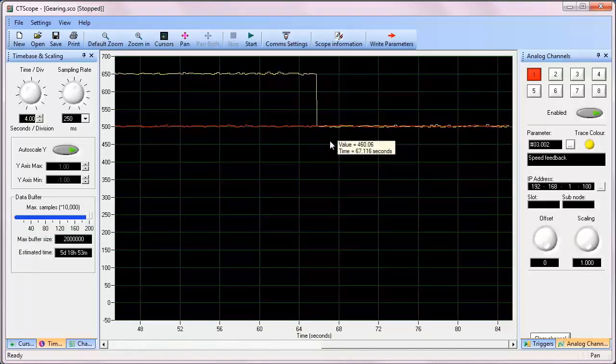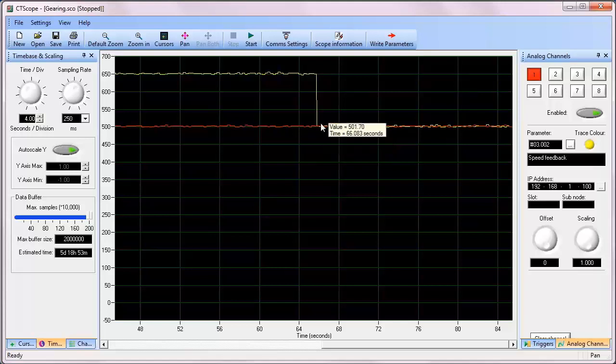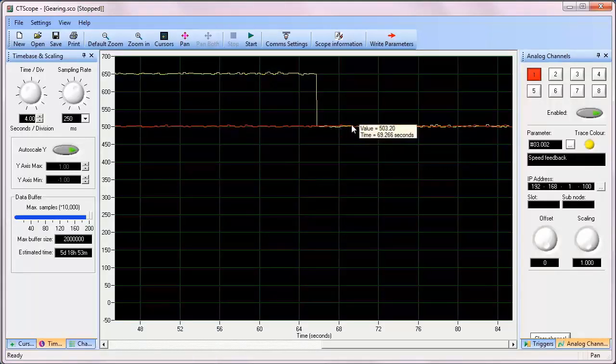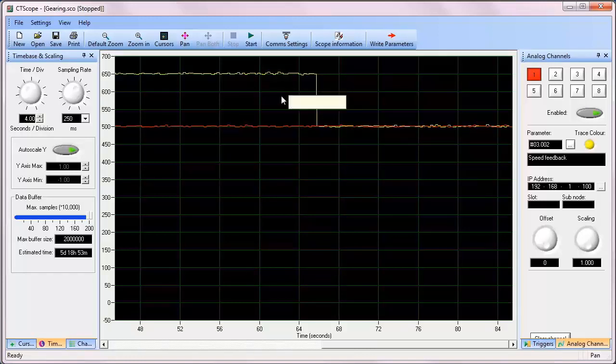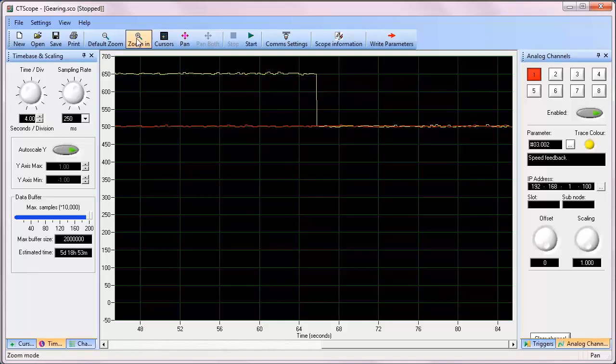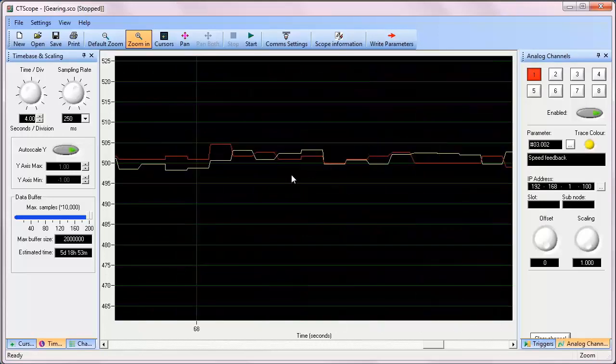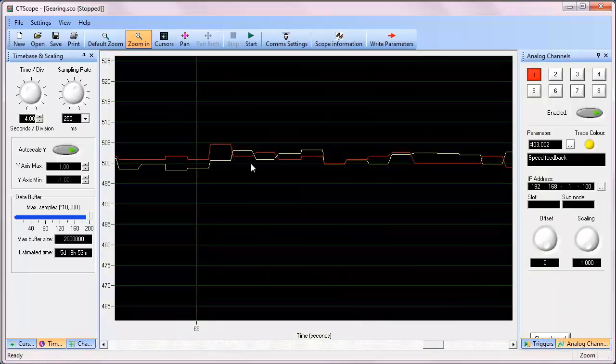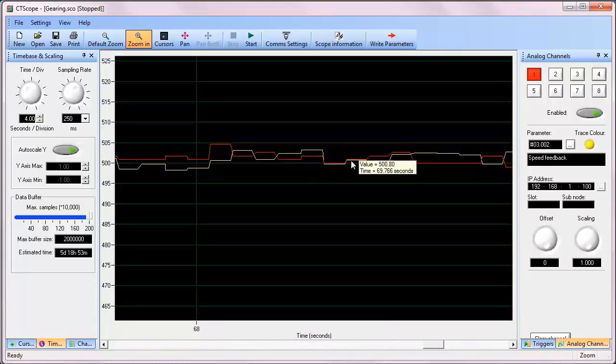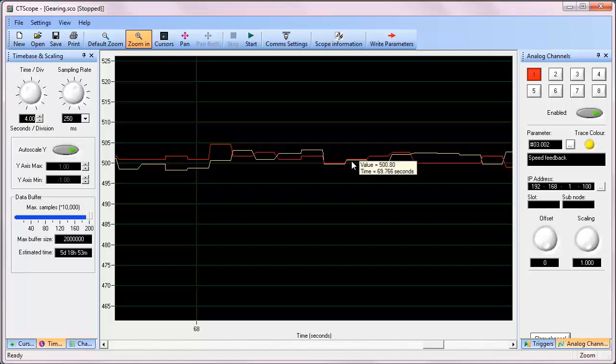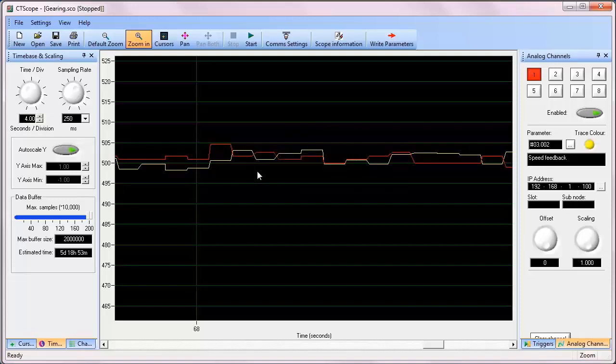Generally speaking, the rigid feedforward is desirable, just for the sake that it really helps to tighten up the relationship between the master and the follower. So now we're following the upper conveyor at the same speed. But what I want to show you here before we move into the next step of the video, is I'm going to zoom in and show you this error. So if I look here, you'll see that we're still deviating here. We're running along at the same speed, but we still have some speed error here as we move along. So if you can envision those two conveyors and the lugs on those conveyors now, even though we're running at the same speed, those lugs are gradually going to be walking away from one another. The position of the upper and the lower won't be in sync, and that's because of this speed error here. So what I'm going to show you next is I'm going to show you how to incorporate a phase advance and phase retard function into menu 13.